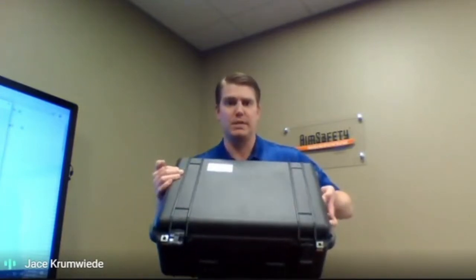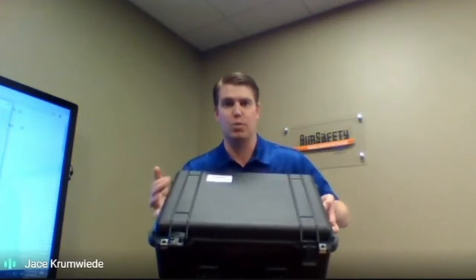Yeah, so it can be bump tested. It can be calibrated. We recommend bump testing before each use. You want to make sure it's working properly, just like any safety equipment. That could be performed using a manual calibration type setup or with a bump test station. What I have in front of me here is a PM400 bump test station, and I'll show you how this works when I get to the 4-gas monitor.